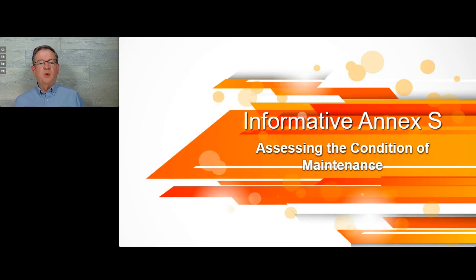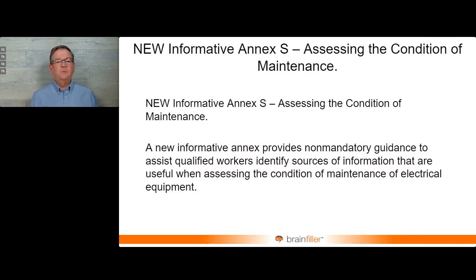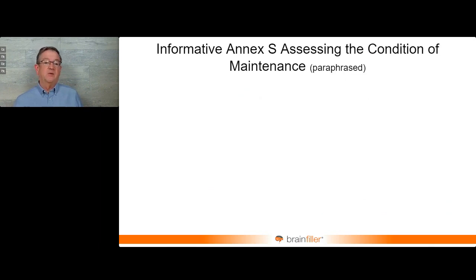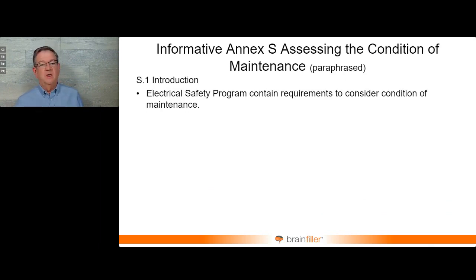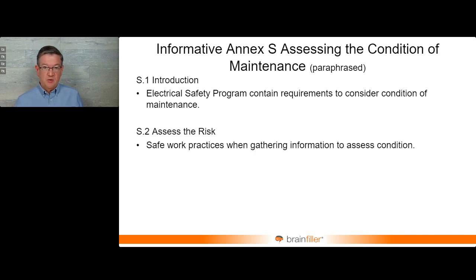And there was a new informative annex. This is about maintenance. Condition of maintenance is used throughout NFPA 70E, but there's not a whole lot of guidance on it. So now there's an informative annex for condition of maintenance. And this is broken up into the electrical safety program should consider the condition of maintenance. And safe work practices are used when you're gathering data for the maintenance. You don't just open it up, hey, what's in here? Make sure you're using safe work practices.